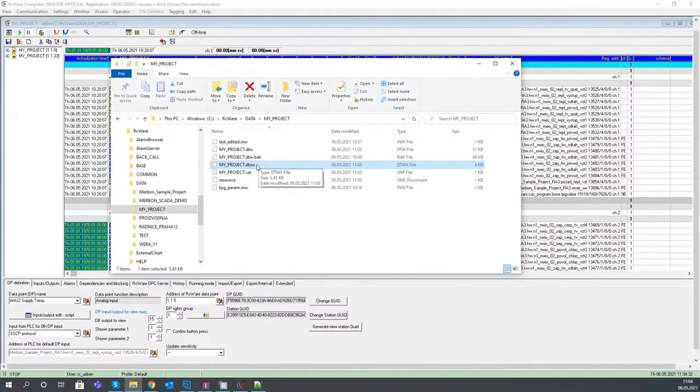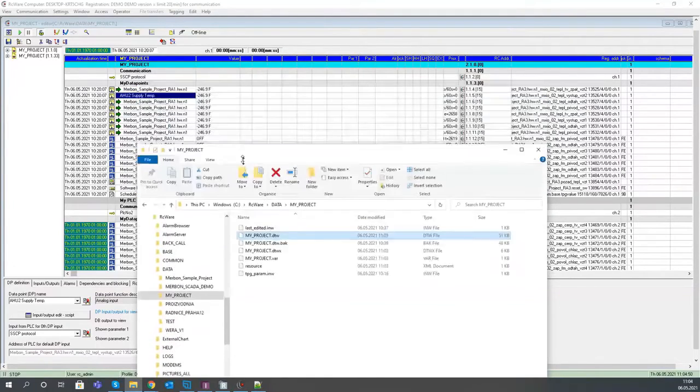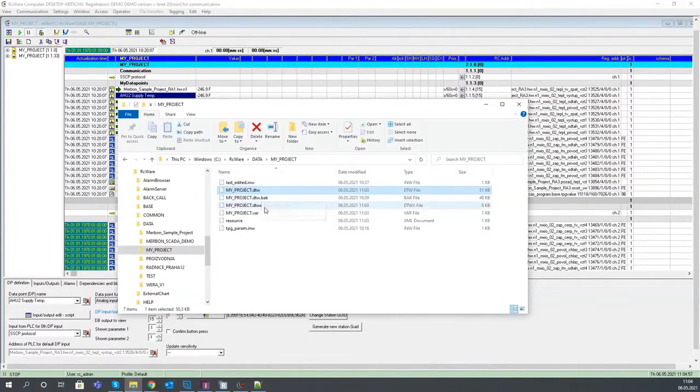just send it to the trash bin, and start the RcWare again. And a new index file will be generated at the program start, and your database will be referenced or indexed properly. So that's what you can do to avoid problems like funny values here. If you, for example, get a temperature of 10,000 degrees, this might be due to the corrupted index file. So let's smash it away and start a new one, and this will be generated automatically.